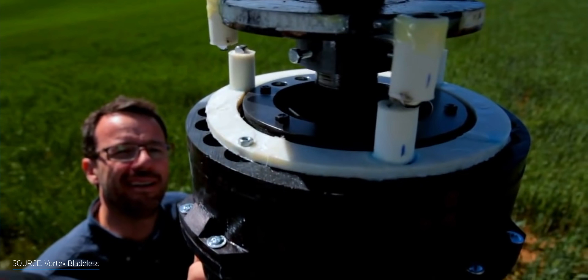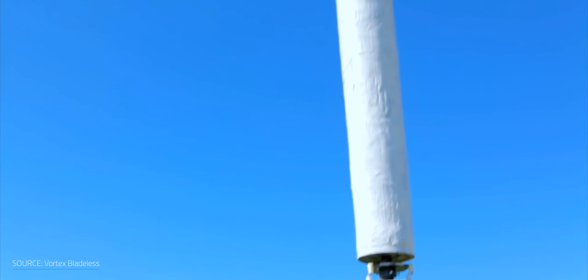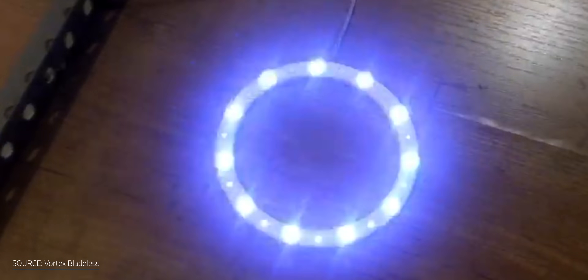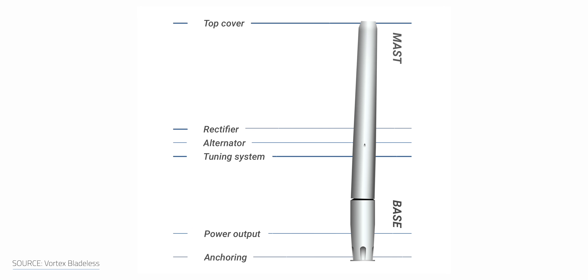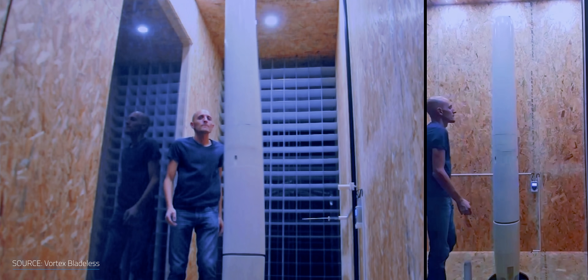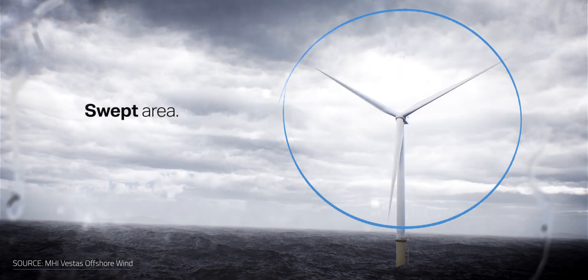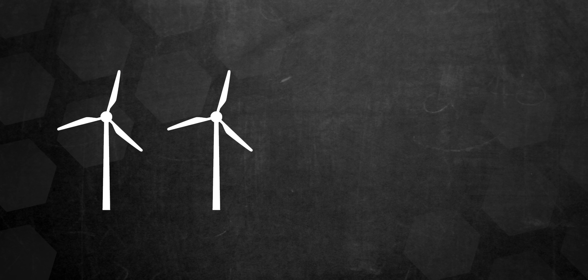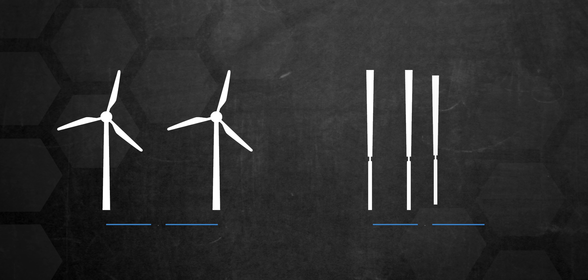Vortex's mast geometry is specifically designed to achieve maximum performance with typical wind speeds. To convert these vibrations into electricity, Vortex Bladeless turbines utilize an alternator system made of coils and magnets that can adapt the vortex dynamics with no gears, shafts, or rotating parts. This design provides reduced maintenance and rules out the need for greasing. This magnetic confinement design acts as a tuning system, increasing the stiffness of the system according to the deformation the wind causes — basically adjusting and synchronizing its natural frequency to match the wind's frequency. If you compare turbines of similar sizes, a Vortex Bladeless turbine harvests about 30% of the swept area covered by a three-bladed wind turbine. The bottom line is that Vortex technology is less power efficient than traditional three-bladed turbines, since power production is proportional to swept area. On the flip side, a smaller swept area means more bladeless turbines can be placed in the same area, making up for that efficiency gap. Running at low to medium wind speeds, it's able to generate the same power for about 45% less cost than a traditional three-bladed design.